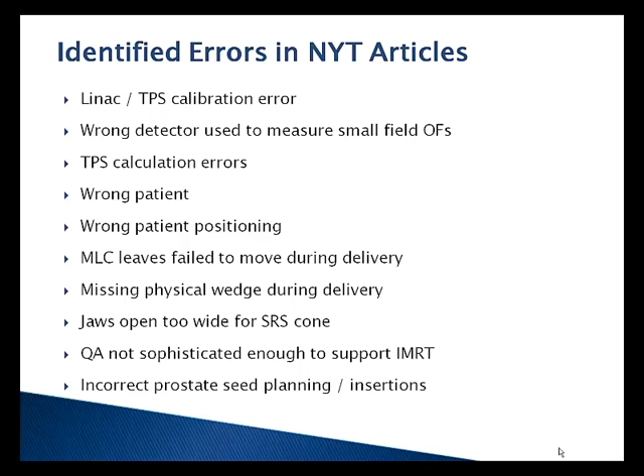Missing physical wedge during delivery. Jaws open too wide for an SRS cone. This is something where the machine did not talk to the SRS cone when it's inserted, so it did not know the maximum field size, and it was input wrong. In general, QA was not sophisticated enough for IMRT, and the clinic moved to IMRT. And then there is a brachytherapy prostate seed error. So, the takeaway message from this is that errors can be hard to see.